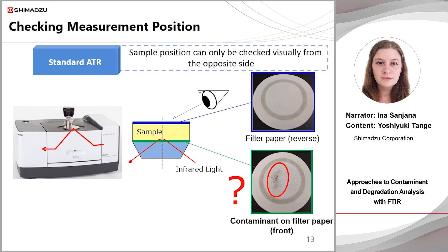There are cases where we want to measure contaminants on the surface of a sample. For a typical ATR attachment, the measurement surface is placed facing downwards and the position is checked by eye. However, it is difficult to see whether the contaminant or discolouration to be measured is in the correct position, because only the reverse side of the sample can be seen. The operator can take several different spectra with the sample in different positions, but there is no guarantee that a measurement will be taken in an optimum position.